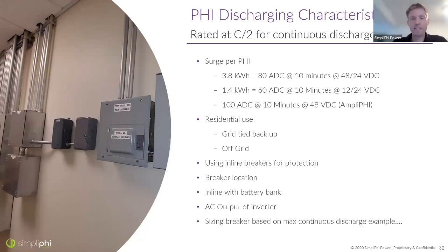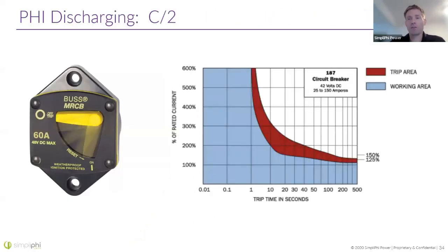Also, always consider the AC output of the inverter. If you are using the inverter as an AC charging source, make sure that you're not charging too rapidly. And be careful on sizing your breaker. So here's a couple of examples of what I was talking about on a breaker. This is a 60 amp breaker, but notice that if I load this 60 amp breaker at 100% of its rated capacity, if I put 60 amps in this breaker, even after 500 seconds, it's still not going to trip, right? So this breaker needs to hit an amperage above that 60 amps in order to trip.